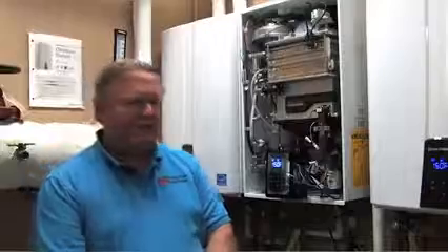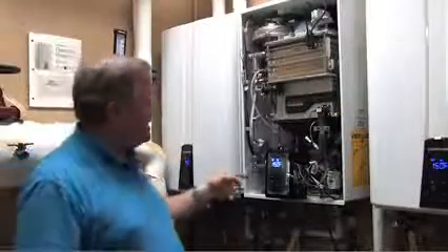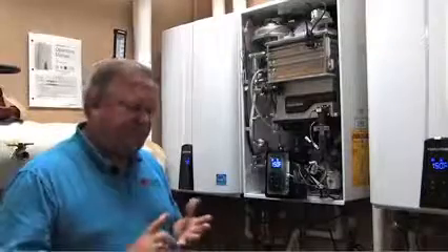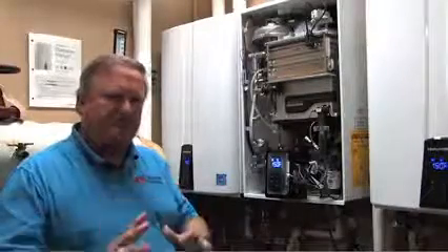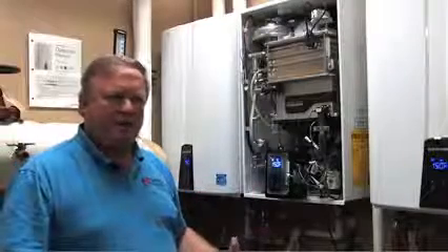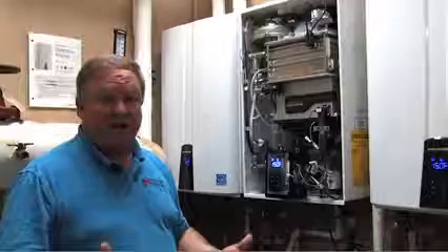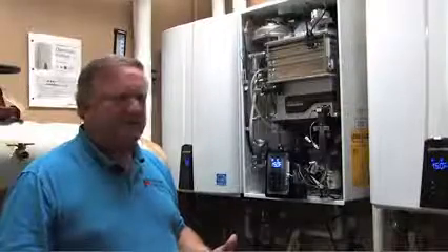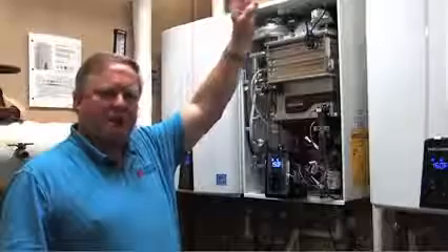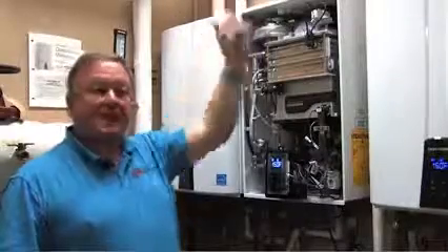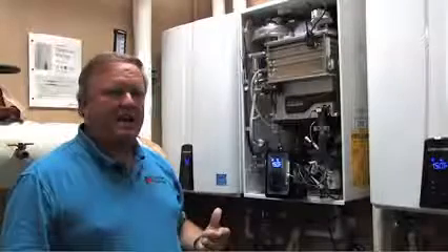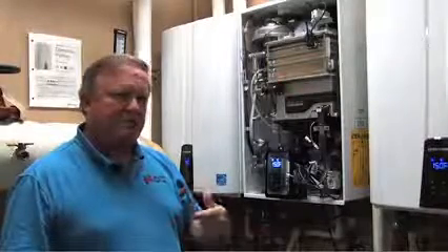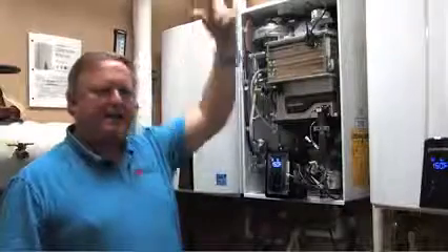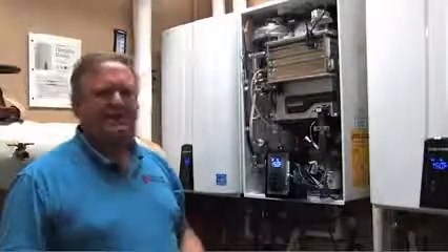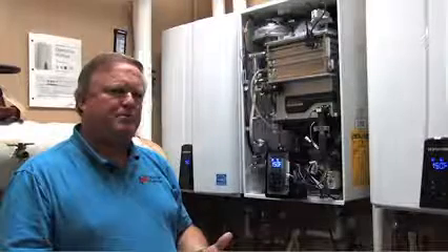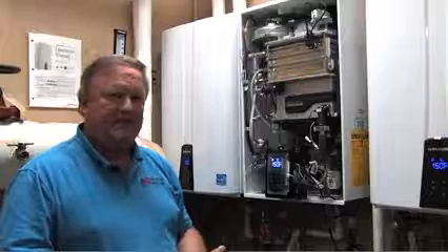The Navien has many other features that aren't so obvious. One is it can utilize a half-inch gas line. That's very important. Most applications, when we go to replace a storage type tank, has a half-inch gas line to it, particularly residential. Not as much commercial, but more residential. So here in the piping up above the water heater would say be a 1-inch gas line with a half-inch drop. In most cases, with any other competitor, they would have to change that gas line from that T all the way down to the unit to 3/4. Not with Navien.